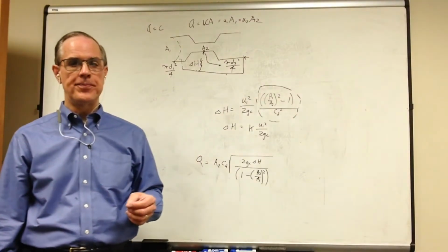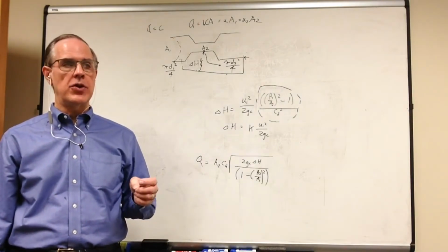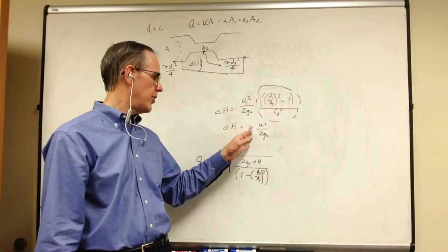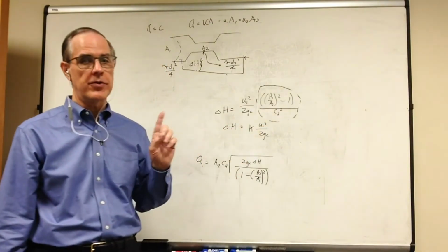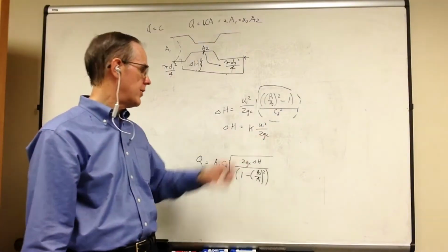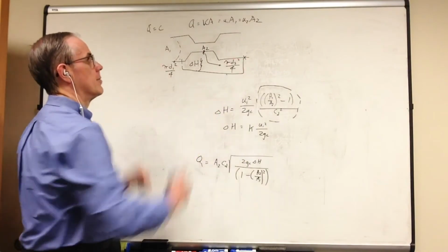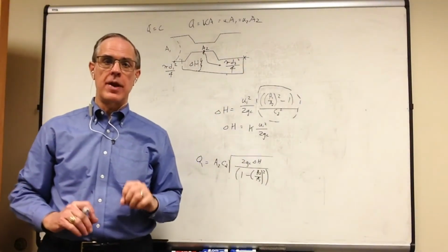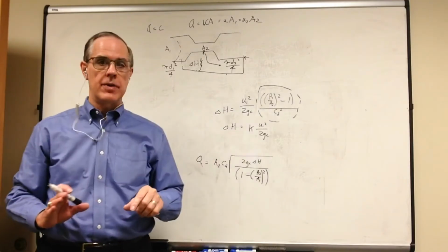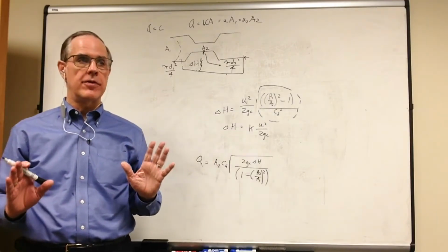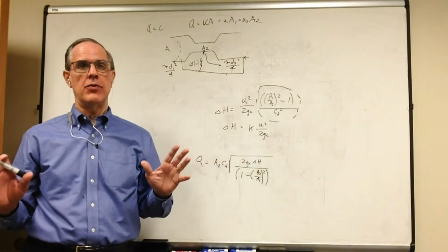So therefore, we can use that if we can measure this quantity. We can definitely measure the inlet velocity, that's inlet U1 squared. g_c is a constant. And we can measure the delta H across the device. We can actually determine what our K is. And we can use that in the operation of the device and in the design of the device and its use in whatever system.